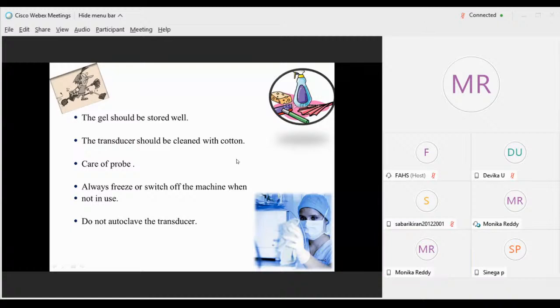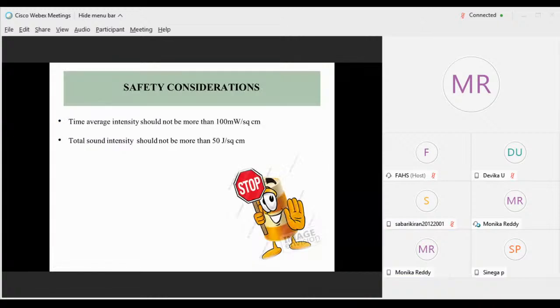And whenever the machine is not used, we can keep it in freeze mode or switch it off. And mention, do not autoclave the transducer. Other than this, the safety considerations are that the time average intensity while scanning should not exceed 100 milliwatt per square centimeter, and total sound intensity should not be more than 50 joules.